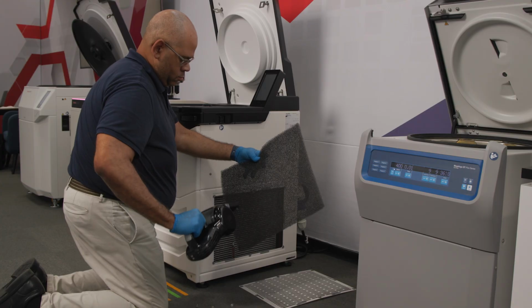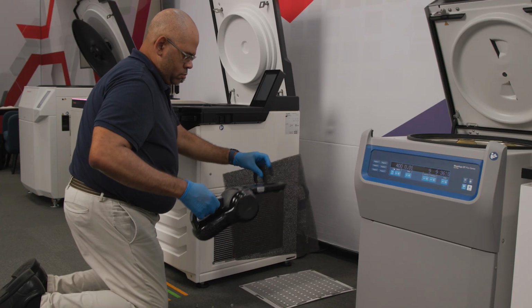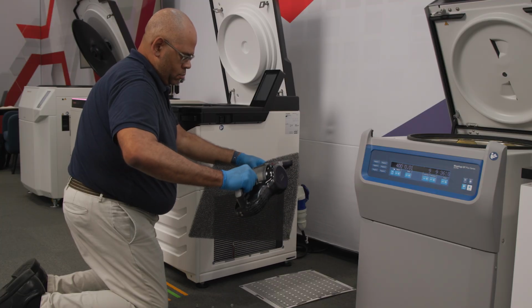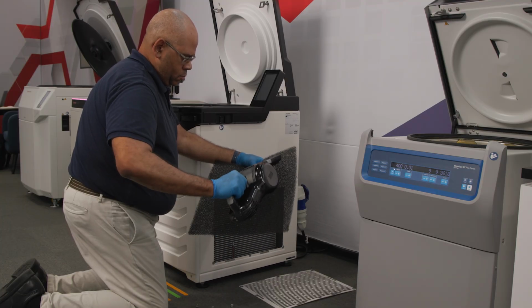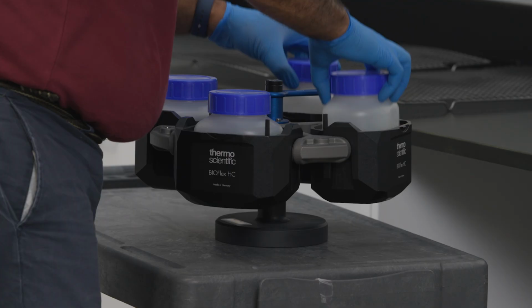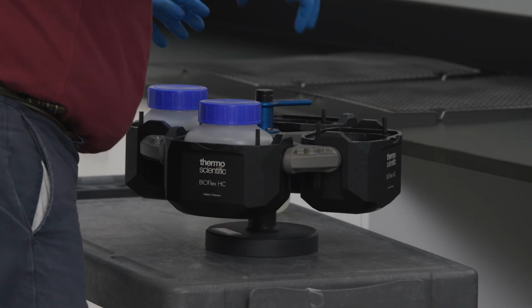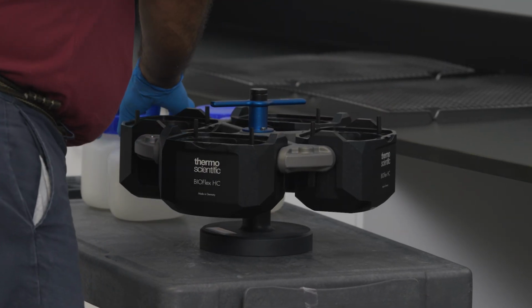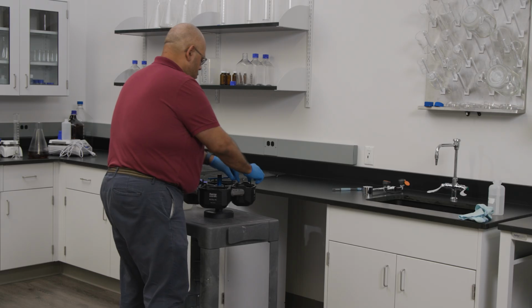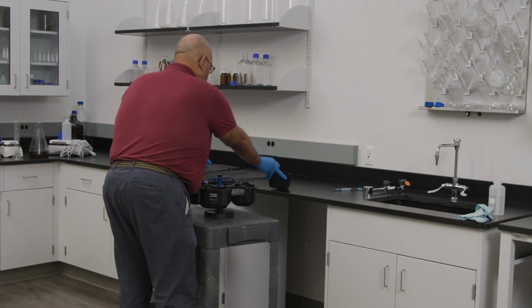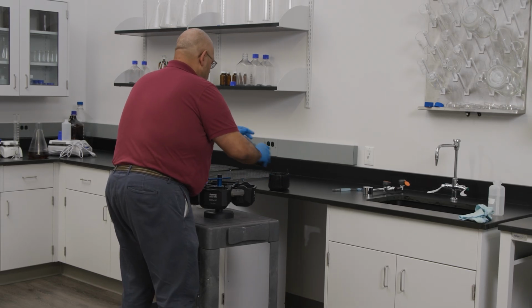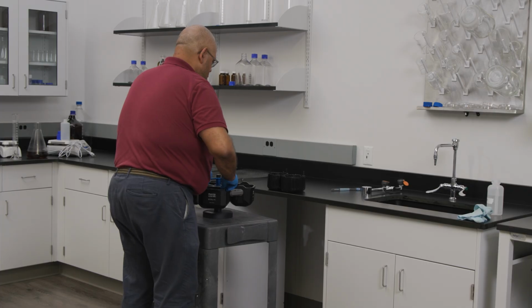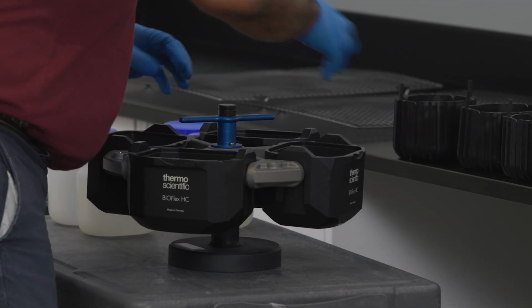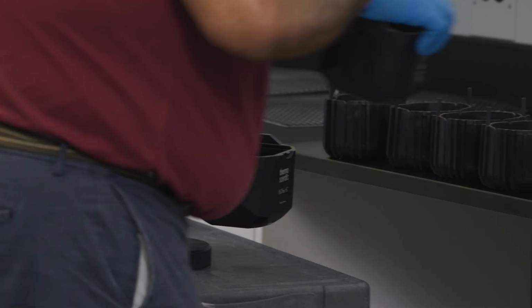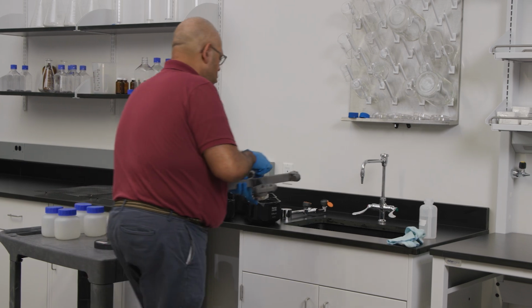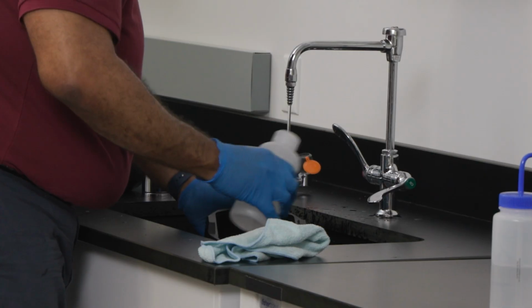The housing should be cleaned once a month, and the condenser filter and ventilation holes should be cleaned every 6 months. To begin, remove rotor, buckets, and accessories from the centrifugation chamber. Separate rotor, buckets, lids, tubes, and sealing rings. If installed, remove the lids from rotors, buckets, and tubes. Do not disassemble accessories using tools or force.